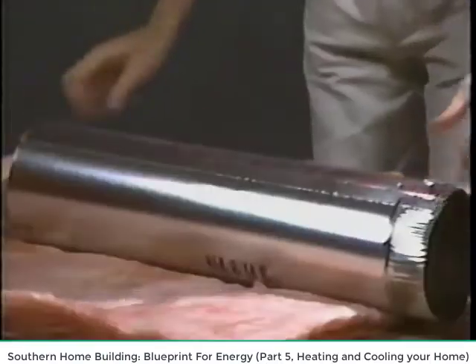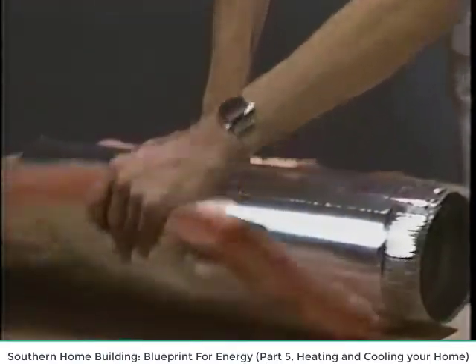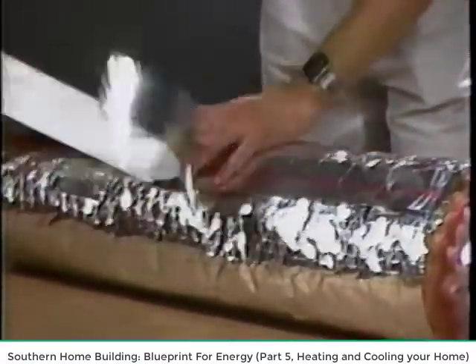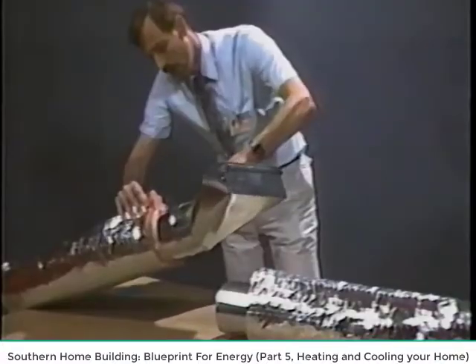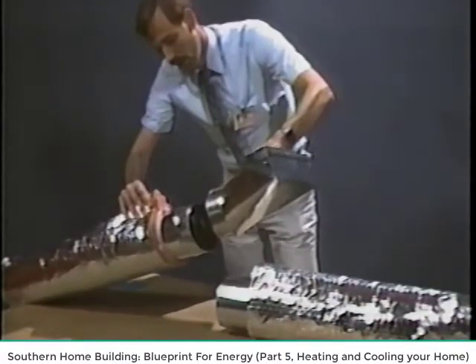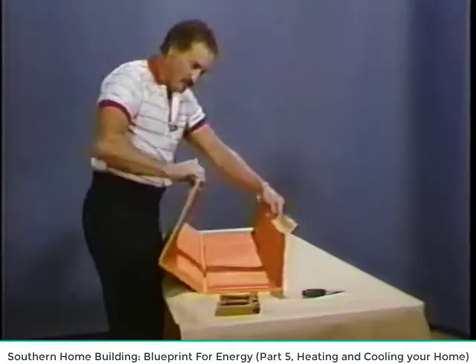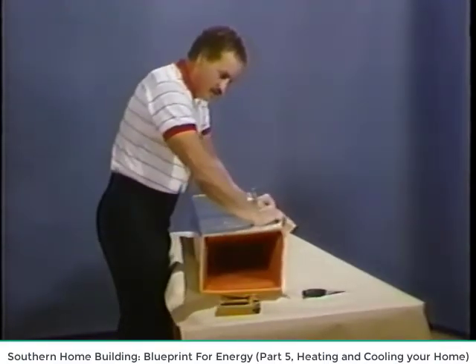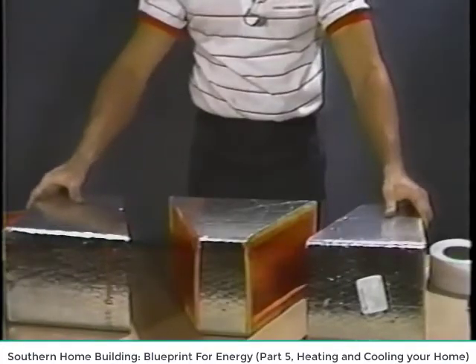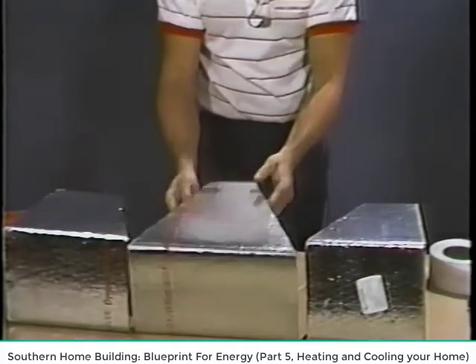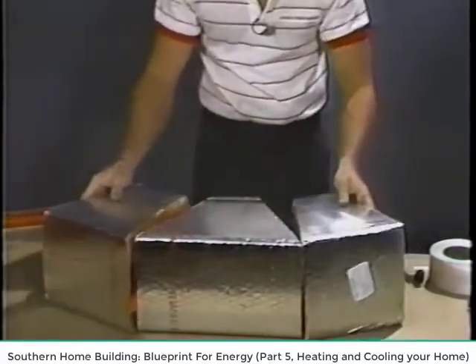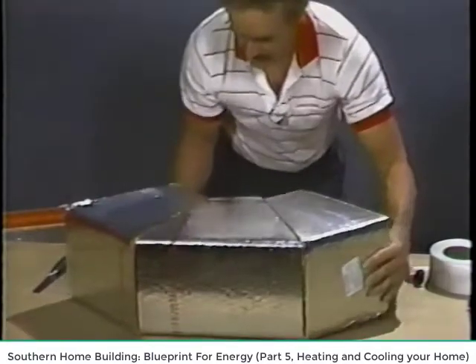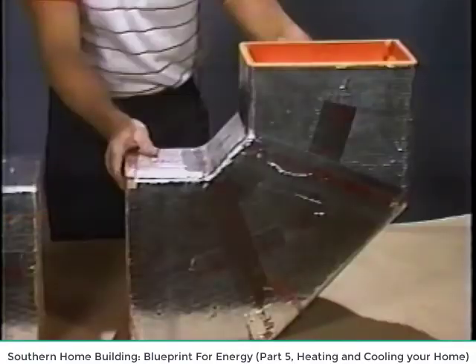One caution: it is very important to seal the seams and joints of the duct carefully during installation, because duct insulation will cover the tape and hide any leaks that may develop. Prefabricated fittings, which require little skill to install, are available. Fiberglass duct board is another type of system. If sealed correctly, it has very little air leakage. Segments of fiberglass duct board can be machine fabricated to help reduce labor cost, but of all three duct types, it requires the highest degree of skill to install.